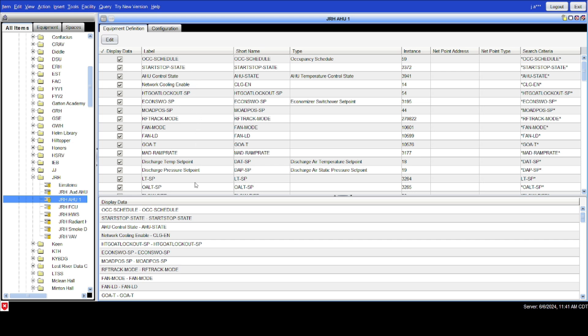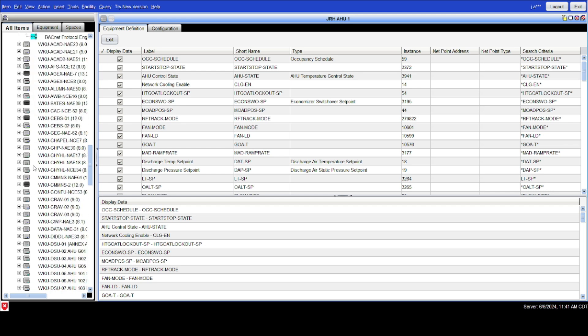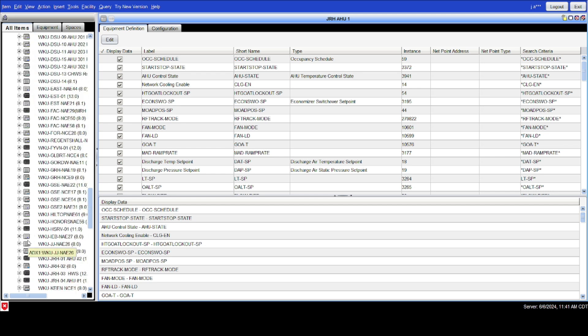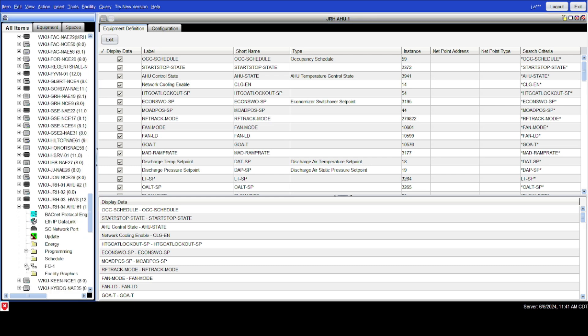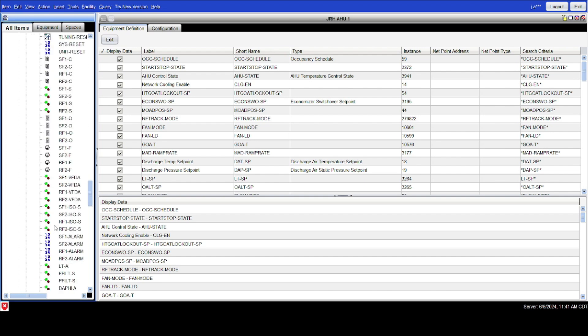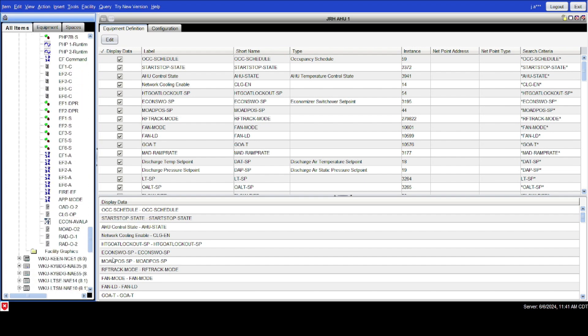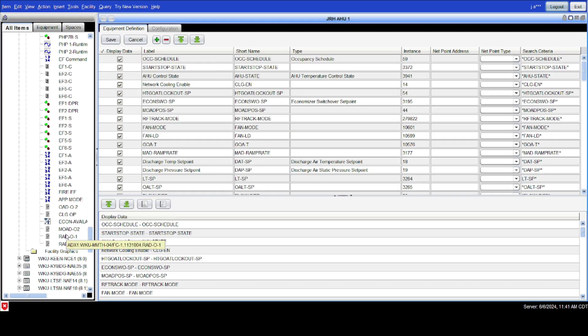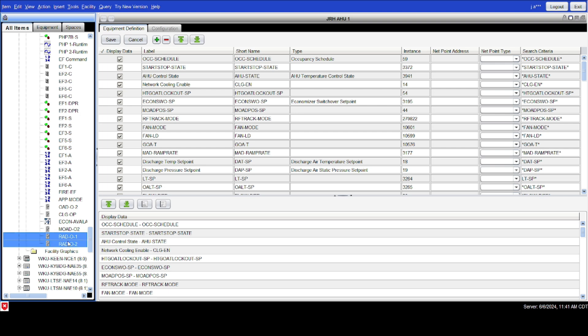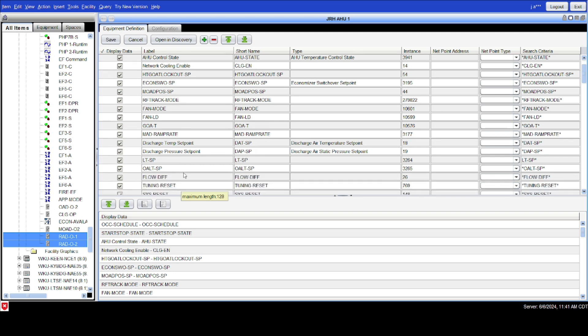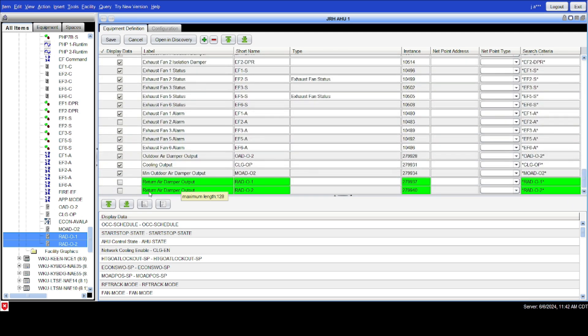This is the equipment definition for that air handler and you can see all of the points we currently have displayed here. The top half is the points that we pulled in; the bottom half of the screen is the order in which they appear, and we can change that by reordering them or by selecting or deselecting each point. We're going to drop down to the air handler, to where we uploaded that network engine, and those two new points are now displayed in the SCT archive. I'm going to hit the edit button and simply grab those two points and drag them over into the panel.